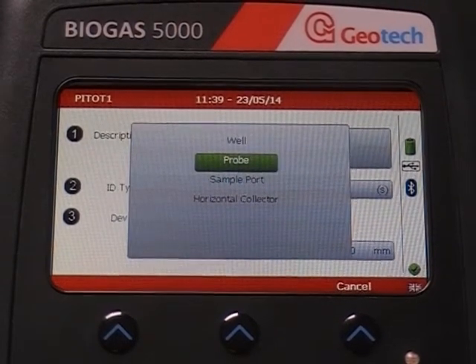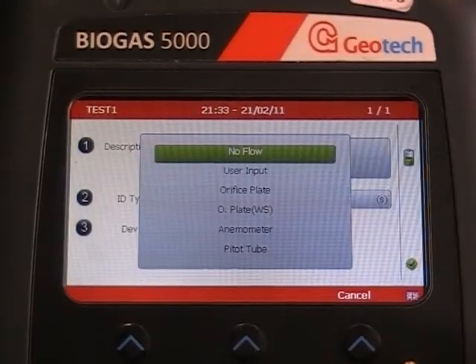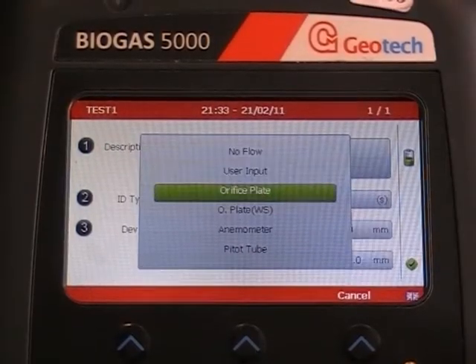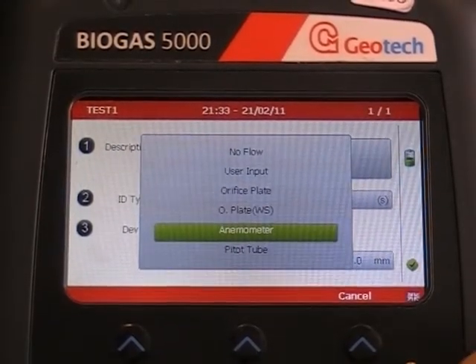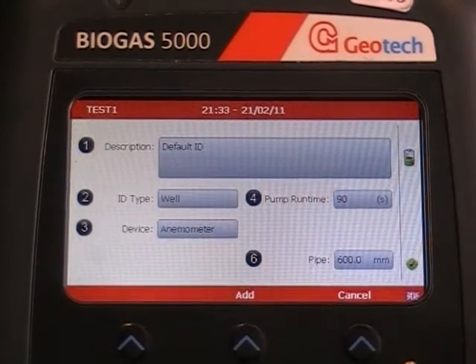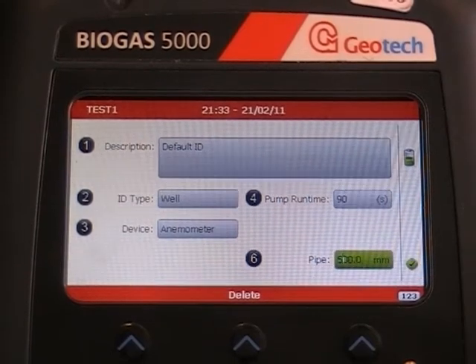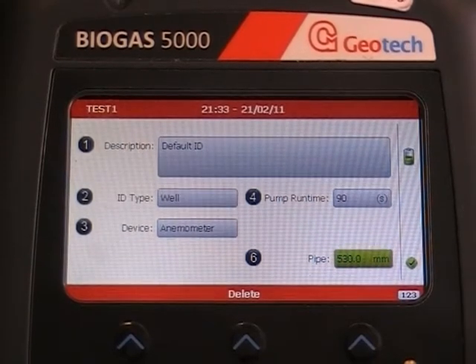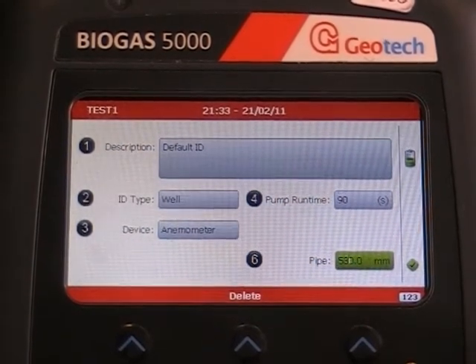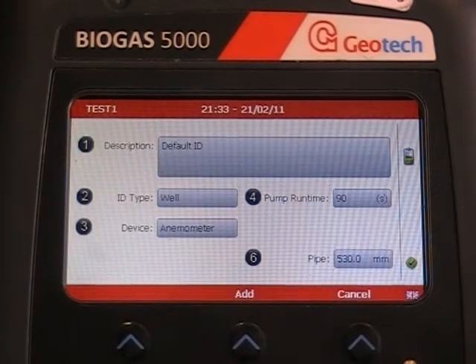Then key 3 for device type, which should be anemometer. Then key 6 to enter a pipe diameter. Doing this allows you to take a flow measurement in meters cubed per hour. Without a pipe diameter, the reading will be taken in meters per second.